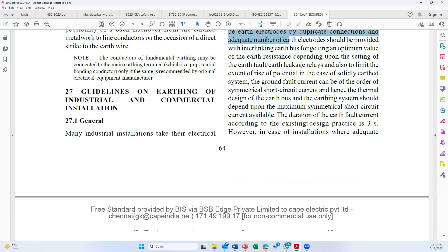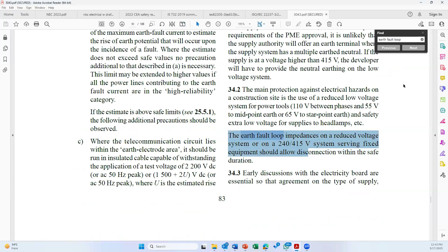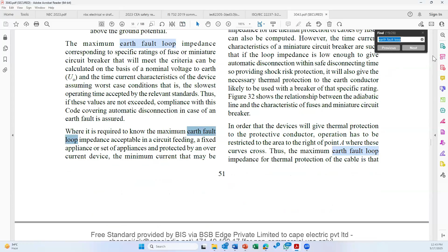Now you see this. As far as the value of earth resistance is concerned, the objective from the point of safety consideration is not to attain a minimum value of earth resistance, as is sometimes understood, but whether there is adequate coordination between the obtainable value of earth resistance and the setting of the protective relays. If you look at this whole document, for example, I'm searching for earth fault loop. You see, earth fault loop has been explained in 26 places. For example, the earth fault loop impedance on a reduced voltage, this is for an ELV system. Let me go back to one of the previous clauses.